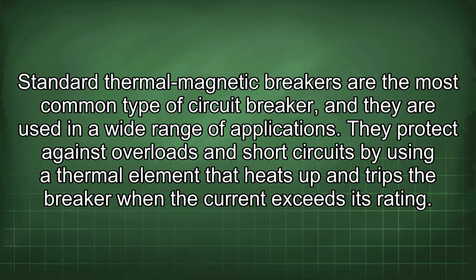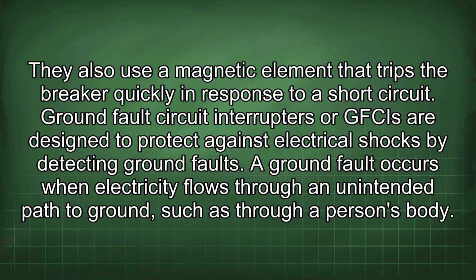Standard thermal magnetic breakers are the most common type of circuit breaker, and they are used in a wide range of applications. They protect against overloads and short circuits by using a thermal element that heats up and trips the breaker when the current exceeds its rating. They also use a magnetic element that trips the breaker quickly in response to a short circuit.